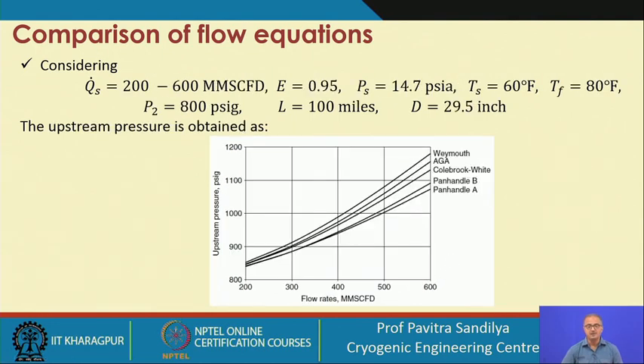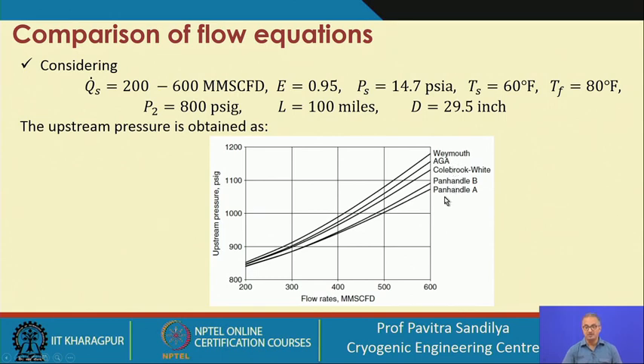Similarly, we can find the inlet pressure from a given outlet pressure. In this case, the range of flow rates is varied while the length is kept constant, and the pipeline efficiency is 95%. Again, Panhandle A gives the lowest inlet pressure whereas Weymouth gives the highest. In both cases — whether finding outlet pressure from inlet or inlet from outlet — Weymouth always gives the highest pressure drop: the most conservative estimate. It is always good to take a conservative estimate when designing or choosing the compressor.